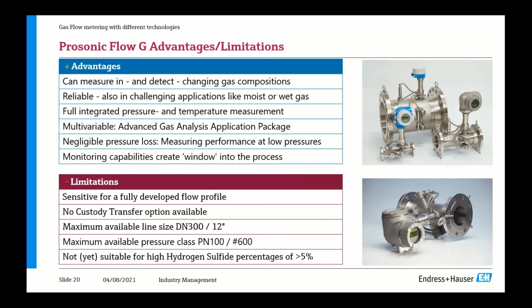We have a very low pressure drop, which means you can measure at very low pressures and low flows. This device measures from a light vacuum all the way up to 100 bar. And based on the monitoring capabilities of the ultrasonic measuring principle, it really creates a window into your process. It can tell you much more about your process than only the flow rate.